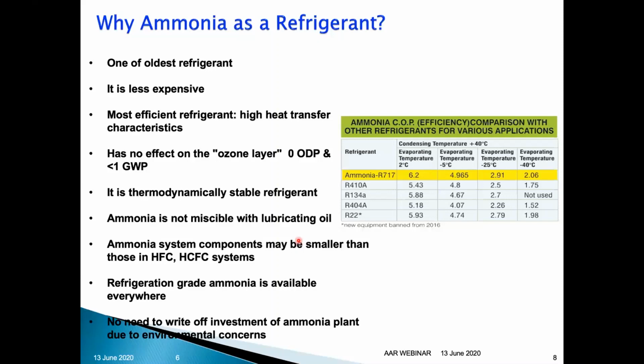Yes, sir. There was this question, and I would like to answer it. You said that it was shown for two different conditions. This is a COP chart at +40, that is, all the refrigerants are compared at the same condensing temperature. You can very easily see the coefficient of performance. Definitely, ammonia is a superior refrigerant, no doubt about it.